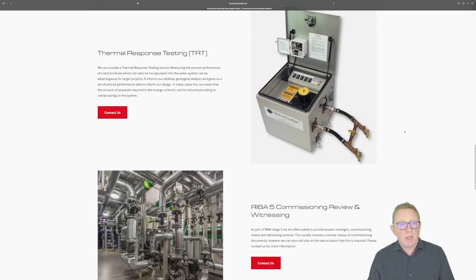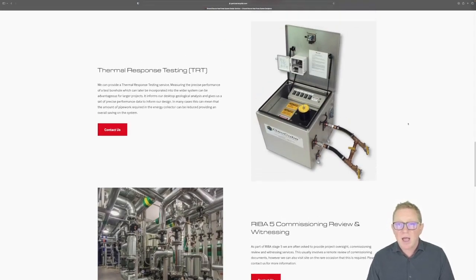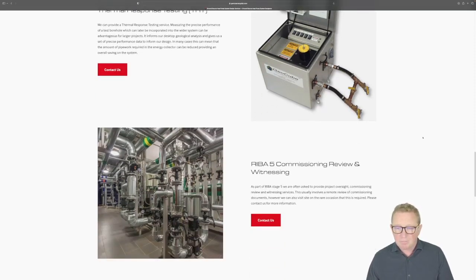Moving on, we provide thermal response testing as well. If you have a site with between 10 and 20 boreholes, it's possibly a good idea and we can give you a steer on that. More than 20 boreholes, it's almost always a good idea to do a TRT test. That gives us the exact conditions of the ground, the thermal conductivity of the ground, and then we can refine our detailed design to hopefully save money on borehole drilling depth.